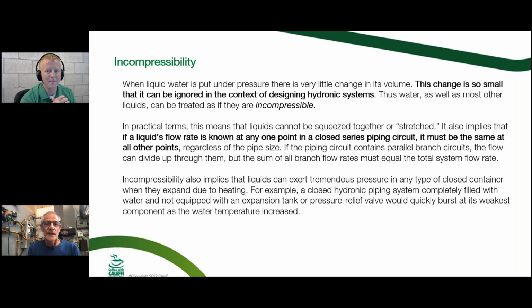Okay. Yeah, so I'm not going to read through this. If you get the slides at the end, you can read through some of these kind of wordy slides, but this came out of one of our hydronics manuals. And basically what we're saying here is you can't squeeze water or fluids, at least under the pressures that we're familiar with working with. And this is one of the things I was forced to look up, I guess. To squeeze water by 1%, it would take 200 times atmospheric, so 14.7 times 200, you could compress water 1%. So obviously that's a big pressure number, not something you're going to typically see in a system that we're working with, residential, even small commercials.